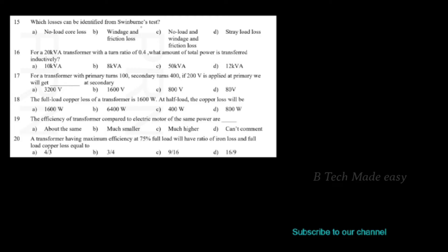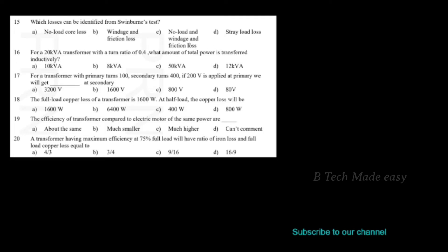Which losses can be identified from the Swinburne test? The options are: no-load core loss, windage and friction loss, no-load and windage and friction loss, or stray load loss. From the Swinburne test, which is conducted at no load, we can identify the no-load and windage and frictional losses. Option C is correct.